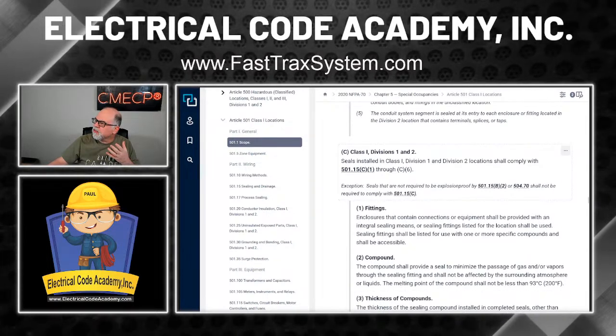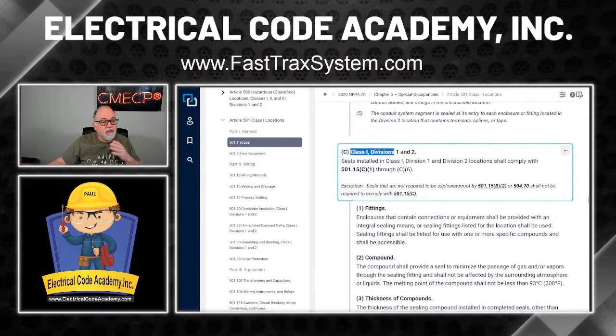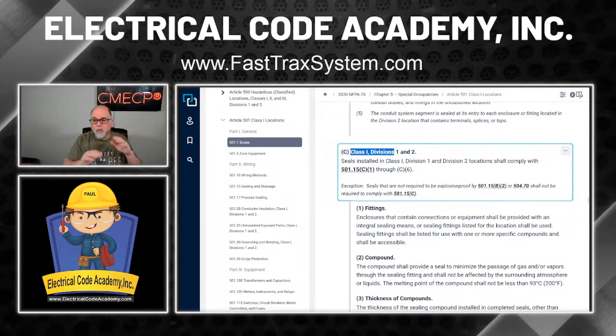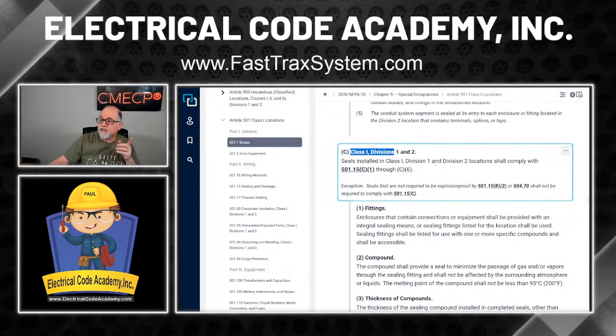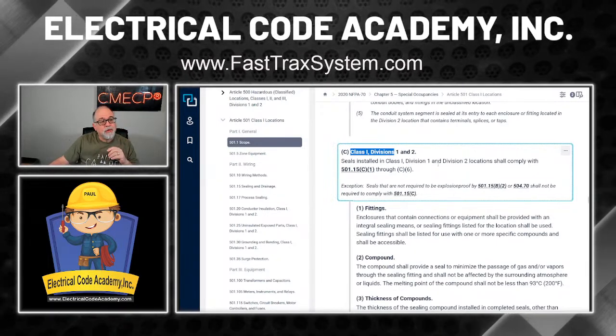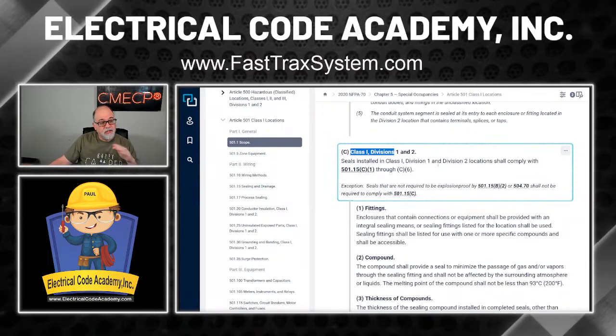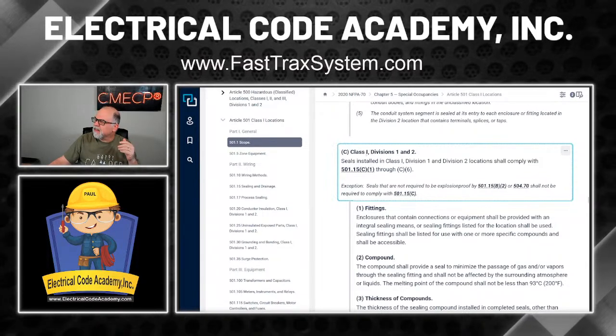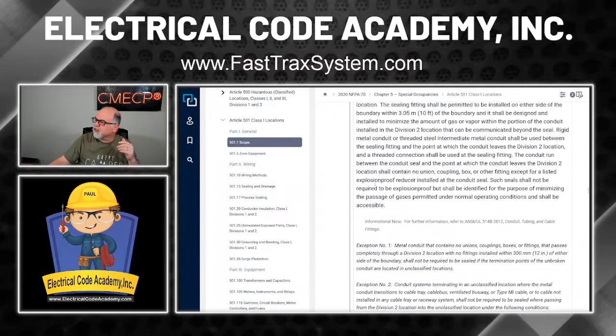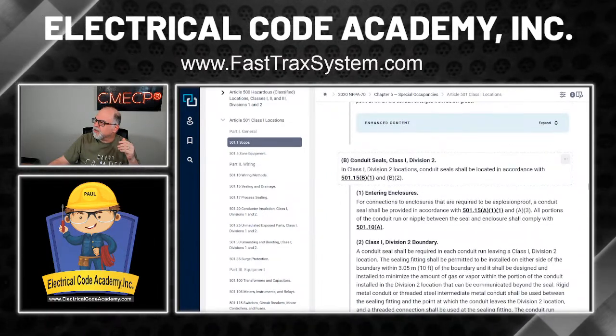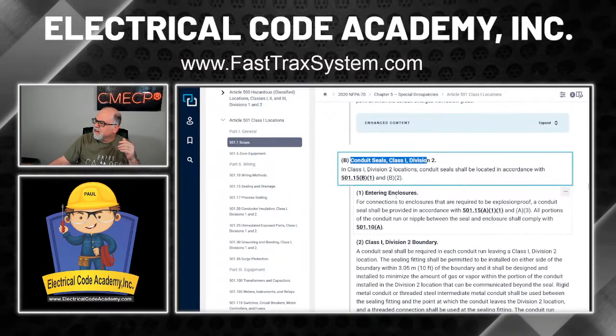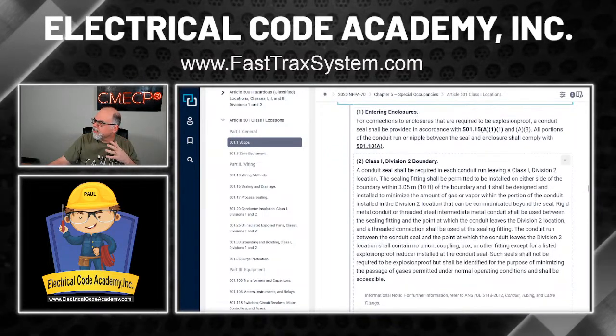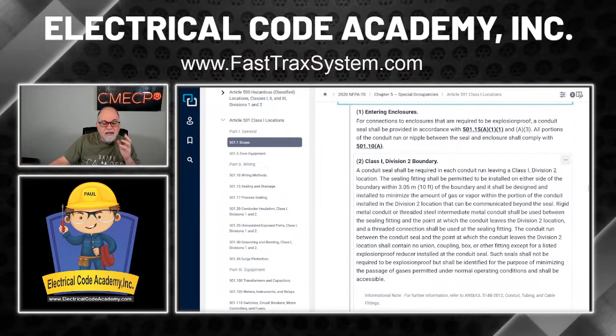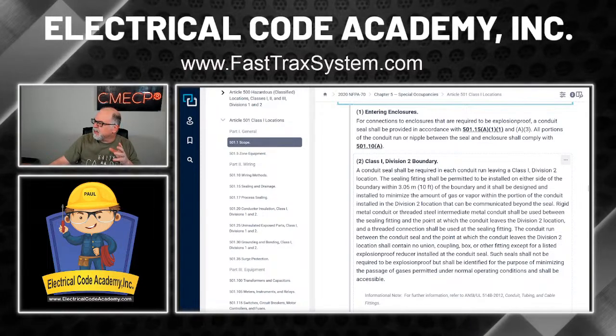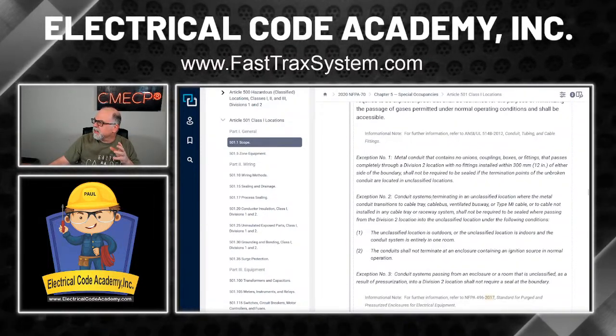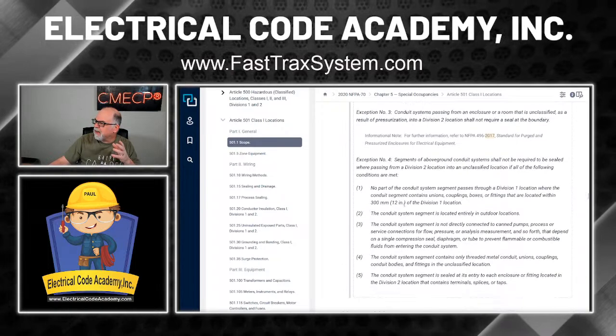And first thing you'll notice is we are dealing with Class 1 in Division 1 or 2. It's either we're dealing with 1. No, actually, the question didn't say whether it was 1 or 2 division, did it? It just says Class 1. So when I see this, and this is under the heading Conduit Seals, now is where I'm starting to look and see the answers, the inch values that are given. And I see nothing in here. Scrolling down inches, nothing matches our answer.